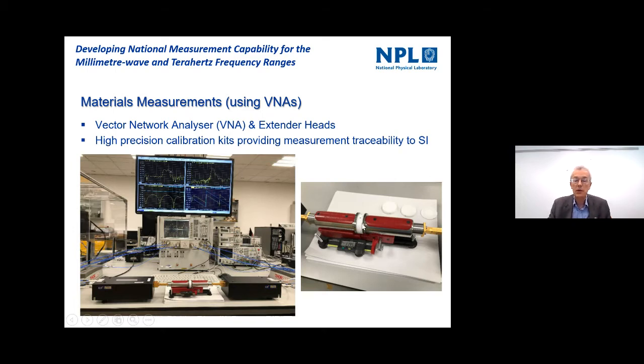So the network analyzer with the extender heads launch waves to measure S parameters. The materials characterization kit then uses that to measure the properties of the PTFE, and it quite literally takes the S parameters and translates them into parameters such as effective permittivity and loss tangent, etc. And it's all done at the push of a button, so it's a very simple and quick technique, and it works in real time. So it's a very powerful technique for making electromagnetic materials measurement, relying of course on network analyzers and these extender heads to give us frequencies in the millimetre and submillimetre wave range.